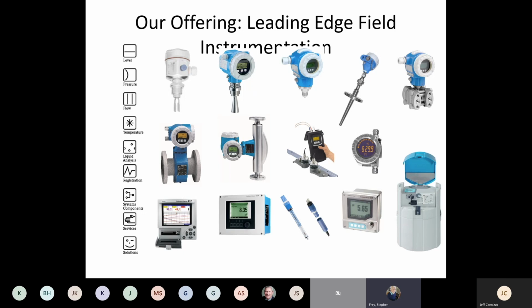We do have a question from Jeff Scott. Do you have any thermal flow meters that have integrated temperature measurement, Jeff? Yeah, the thermal mass principle is temperature. It's actually temperature sensors in there. And yes, besides flow, you can also output process temperature. So you can output the gas temperature as well as the flow, if I'm answering the question. The meters have multiple outputs. Great, thanks, Jeff.